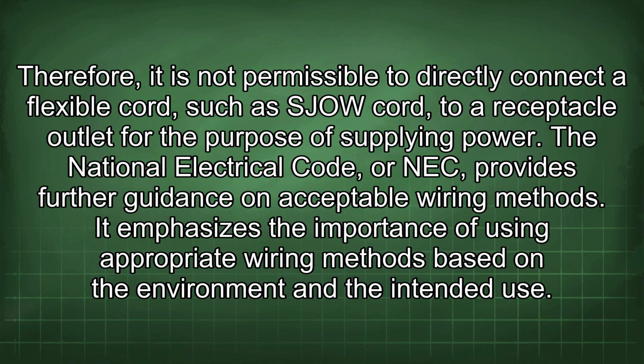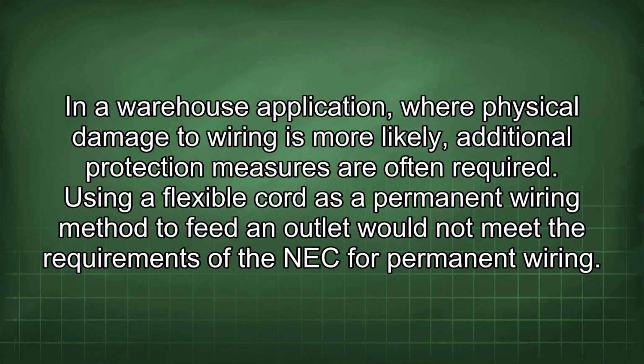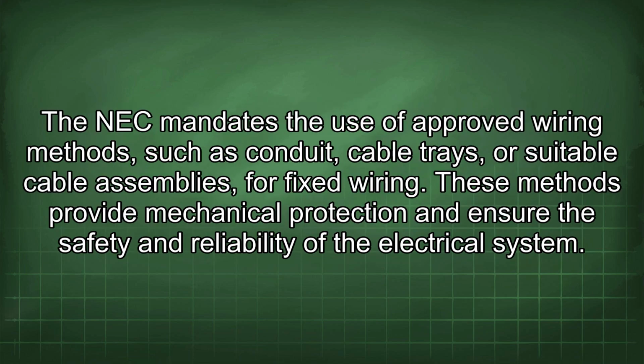The National Electrical Code, or NEC, provides further guidance on acceptable wiring methods. It emphasizes the importance of using appropriate wiring methods based on the environment and the intended use. In a warehouse application where physical damage to wiring is more likely, additional protection measures are often required. Using a flexible cord as a permanent wiring method to feed an outlet would not meet the requirements of the NEC for permanent wiring. The NEC mandates the use of approved wiring methods such as conduit, cable trays, or suitable cable assemblies for fixed wiring.